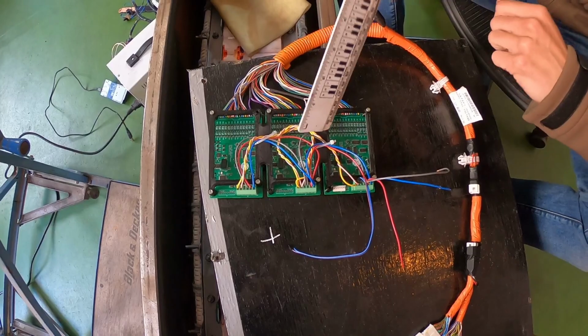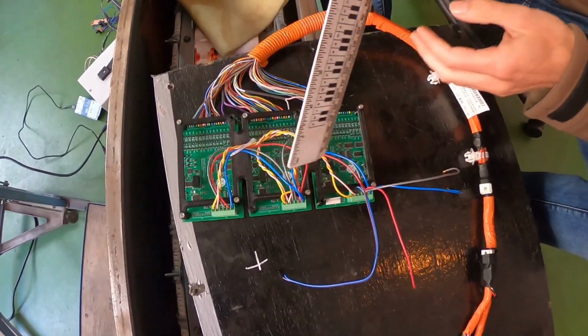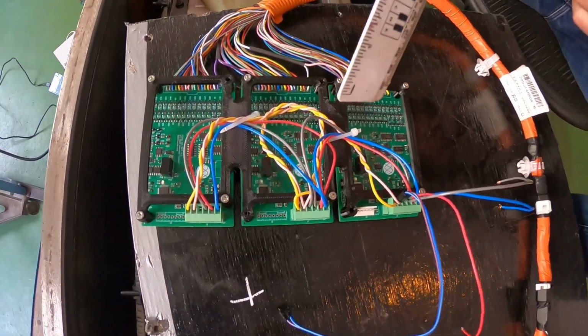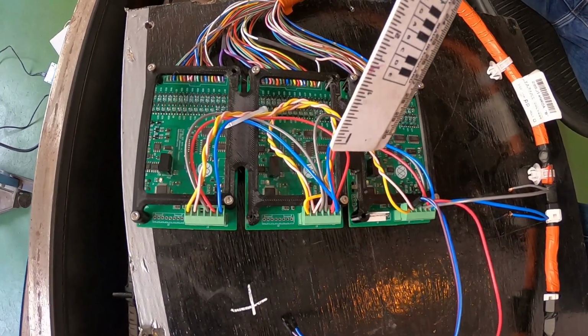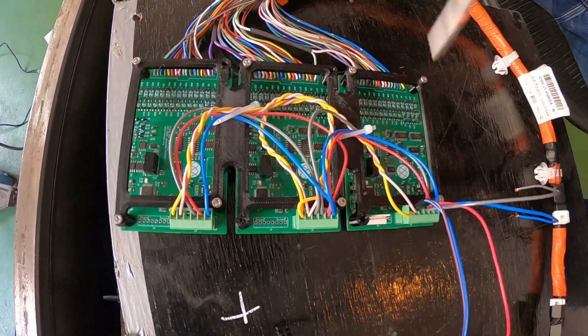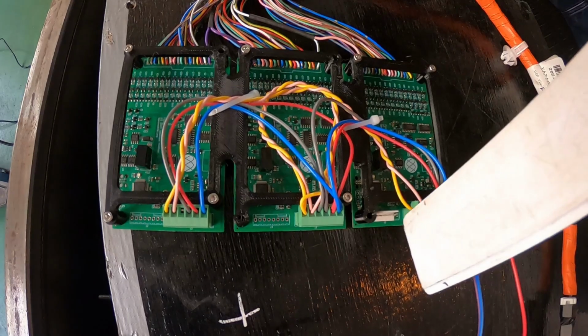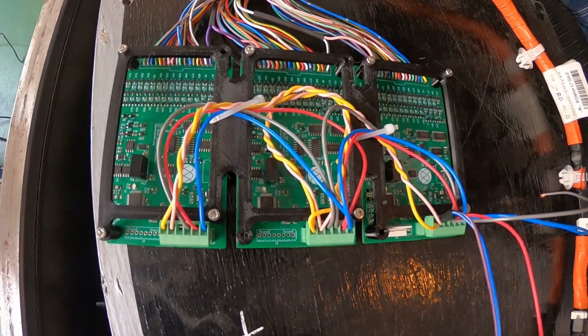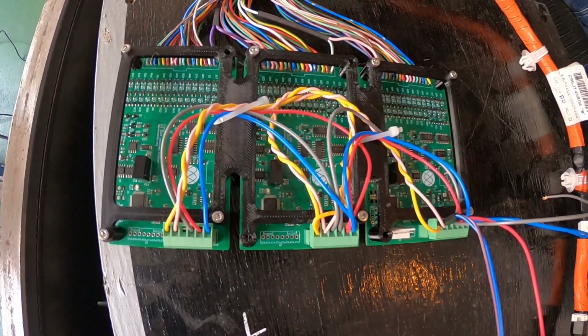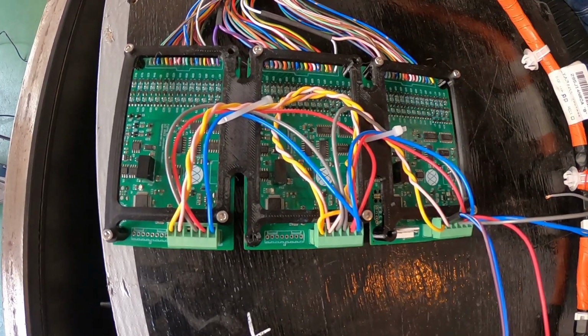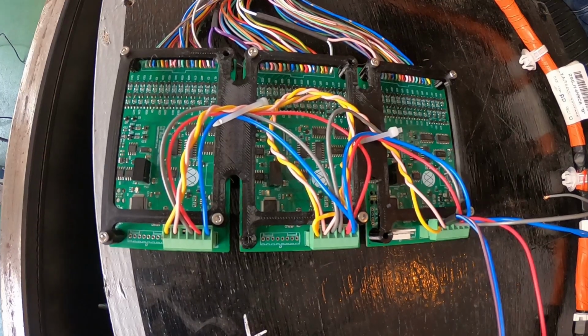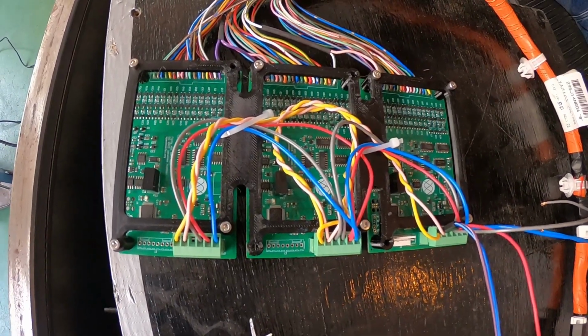Another feature of a BMS is to measure the current being put in or drawn out of the battery, and also to measure its temperatures. That's why each module has 2 temperature sensor inputs and 1 current sensor input. You don't have to use it, but you can, and just use the module that's closest to the respective sensor to read it.